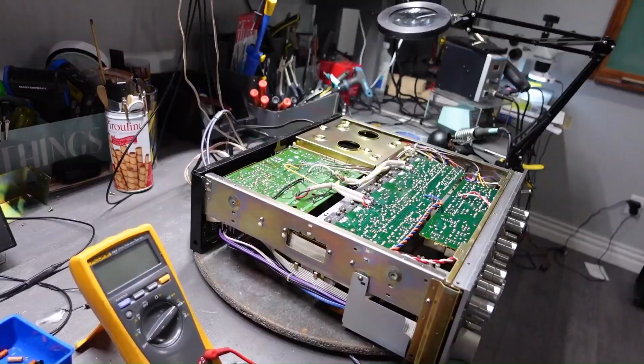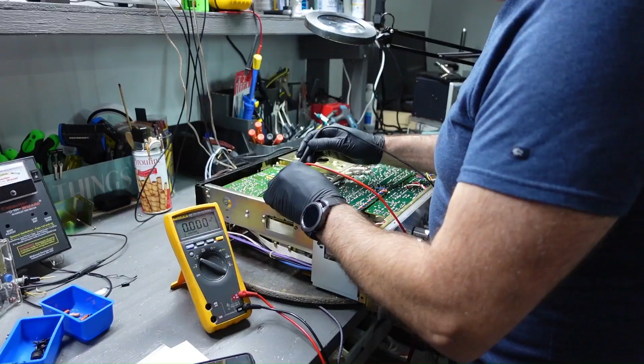Since this amplifier is running really high voltage, I am going to check. Remember the 4 filter capacitors. I know they're holding charge, and before I put in my capacitor wizard on here, I'm going to have to discharge this. Okay, so there's 1 volt on that one. See, there's 45 volts here. 44 and 44. Not sure why there's only 1 volt on this one. I will be checking this filter capacitor. Not sure why there's no voltage on that, but I need to discharge this before we do anything.